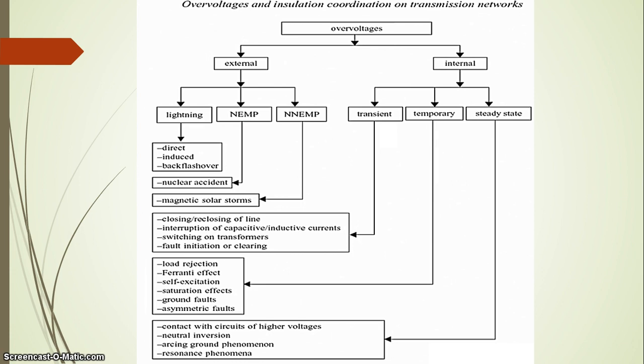In the steady state category of internal overvoltages, the causes include contact with circuits of higher voltages, arcing ground phenomena, neutral inversion, and resonance phenomena. The most common internal overvoltage is transient overvoltage, caused by switching of capacitive and inductive elements, transformers, faults, and closing or reclosing of lines.